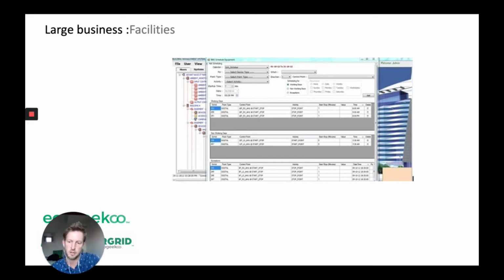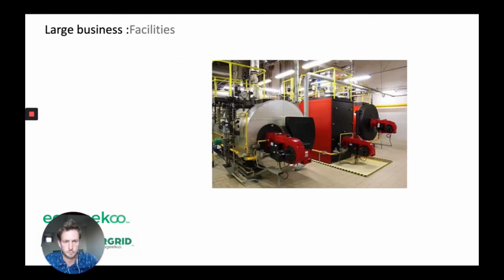So if your facility is just straight up offices, quite simple, fairly minimal impact. If you do have labs or pressurized environments or anything that might require aspects of dehumidification, then you've got to be more careful. And also the same goes if you have server rooms. But working with your controls engineer, they should be able to help you identify fairly low risk things that could be switched off. It's going to be your best friend. There's some significant energy savings that could be made through simply switching things off through the scheduler or programming them to reduce the time they're running for.